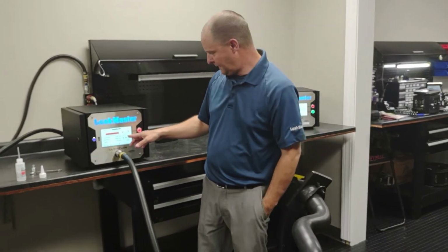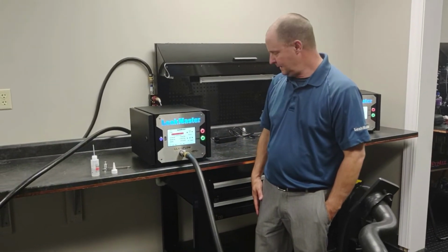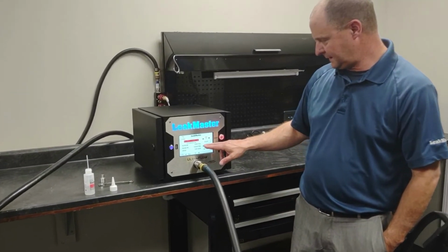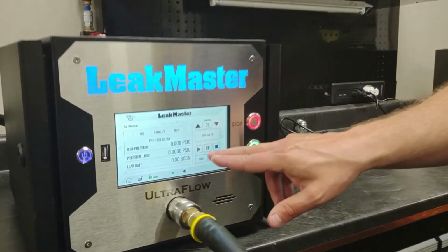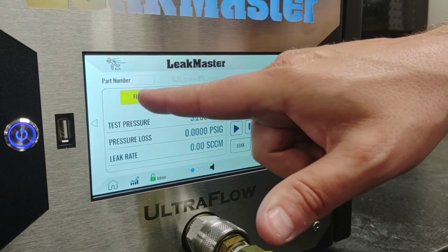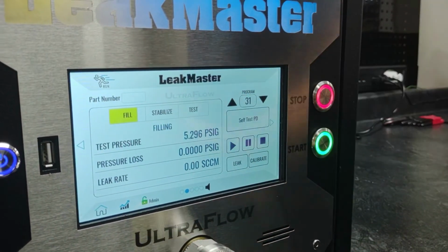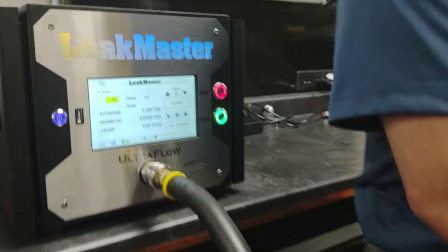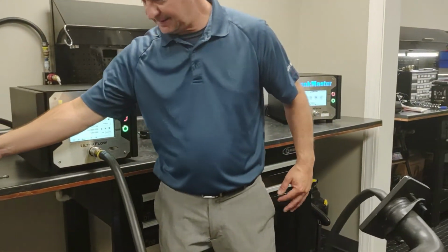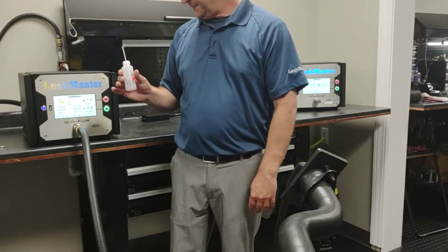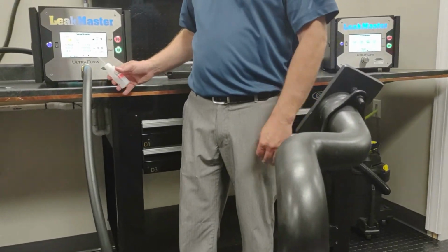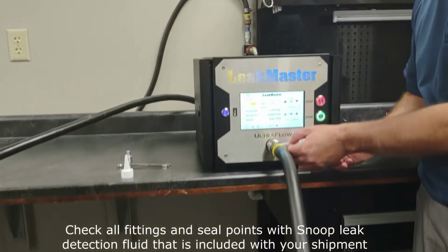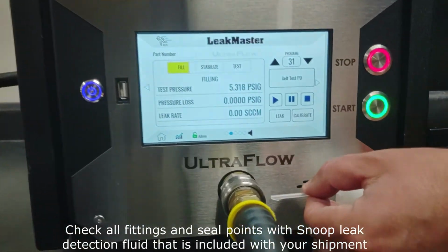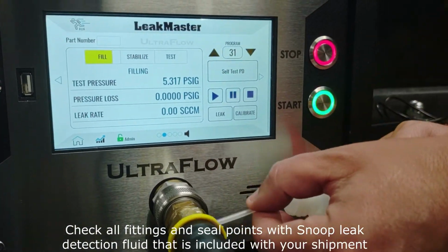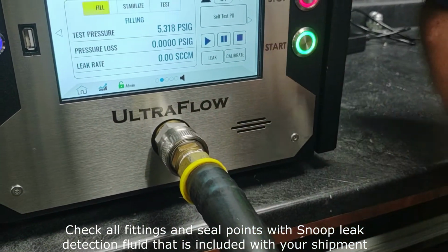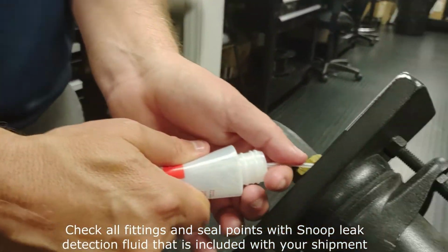I'm still on the self-test program here, so I'm going to start this test. I'm going to hit start. I'm going to immediately pause it during the fill step. You can see it pause during the fill status. All I'm doing is applying 5.3 psi to this product. And I'm going to check every joint to verify that I'm leak free. Make sure there's no bubbles coming out. I'm going to test every joint.